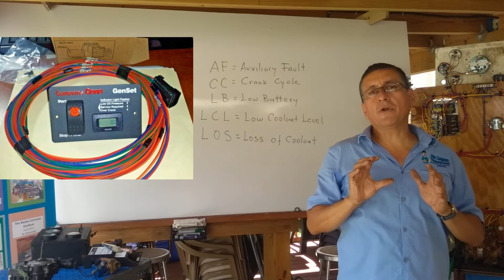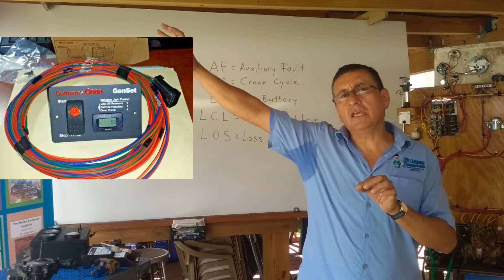If you have that code flashing on the display of the computer, that code, auxiliary fault, indicates that the problem is on the harness outside of the generator. It's not on the generator, it's outside of the generator. It's between the generator and the remote panel. You have a problem in the harness that you have on the screen or on the remote panel. You need to identify where the interruption is. Normally it's an open circuit. It's a cable that is cut or interrupted, or loose terminals. In some cases, this is the problem. This is auxiliary fault. It's a problem outside of the generator.